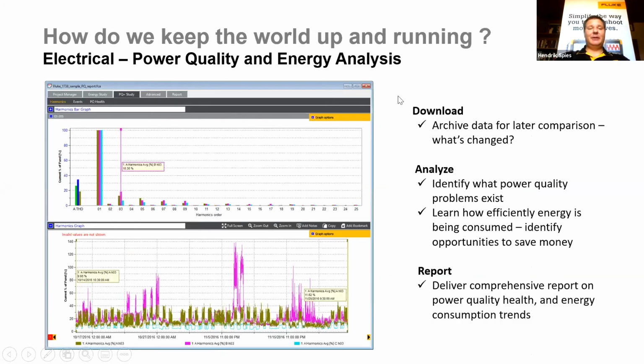Okay, last but not least on energy and power quality analysis is the software. We've got a comprehensive software suite that actually will help you to download the data from your actual test set. It will help you to analyze the data, and it will help you to generate reports. So this is the Energy Analyze Plus software. And as you can see, number one, you've got a project manager. This is typically all the information on the actual test set use, serial number, number of logs, and quite a lot of information, thermal images, images of the actual plant itself or the substation. So here you actually put all your documentation type information.